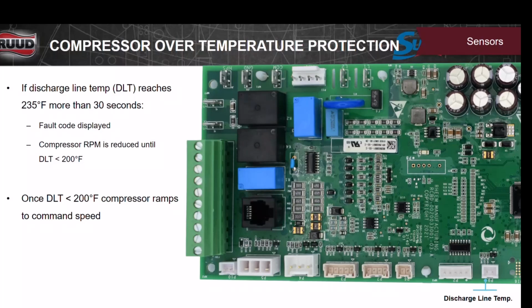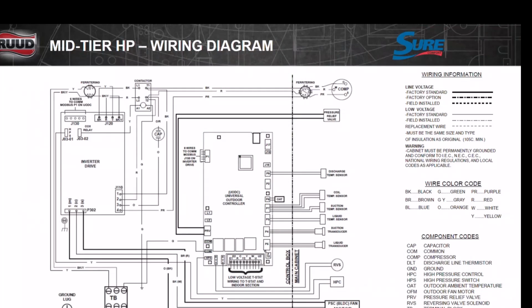If it continues to do this, that's when it's going to throw that code. If it doesn't line back out after it goes down to 200 and then goes back to the command speed, and it goes back up again, then we're going to have problems with the thermistor or something, or it could possibly be undercharged. This is just a schematic that tells you where all the thermistors are located on the board. Of course, it was marked on the board like it was before to tell you where it's at.